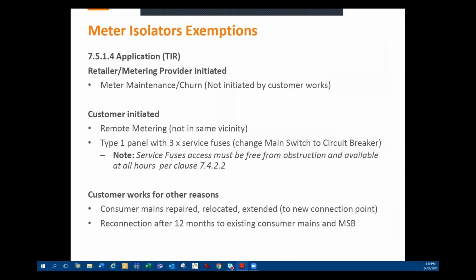With meter isolator exemptions, clause 7514 for the application, retailer or meter provider initiated work: if it's meter maintenance or a churn, so it's not initiated by the customer, there's no requirement to install that meter isolator, because obviously an electrician shouldn't be involved in anything like that. If it's customer initiated, where it's remote metering and not within the same vicinity, meaning the same area, so if the main switchboard is totally separate from where the metering is, then it doesn't need that meter isolator.